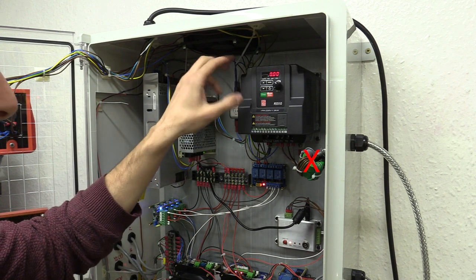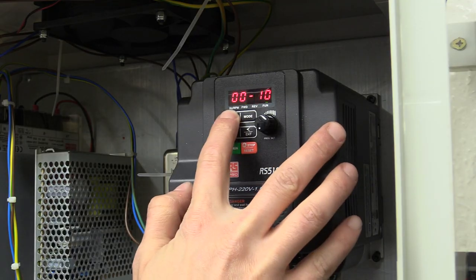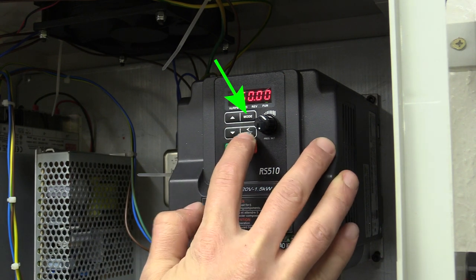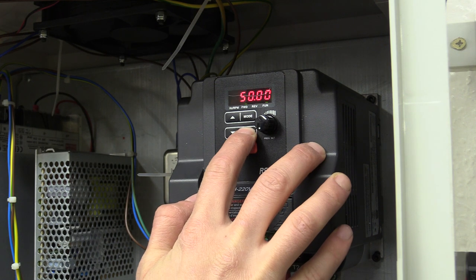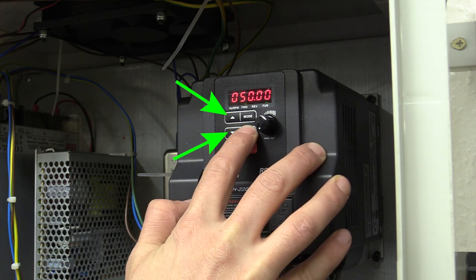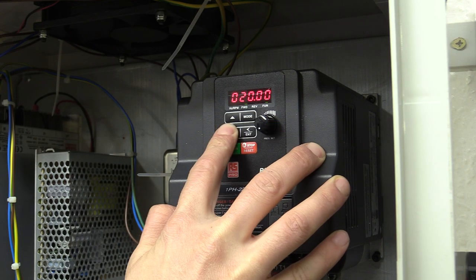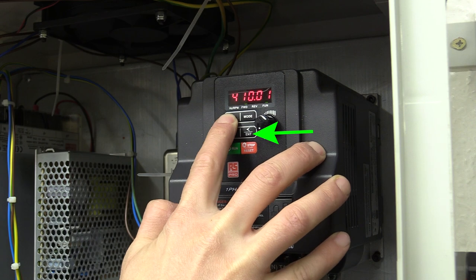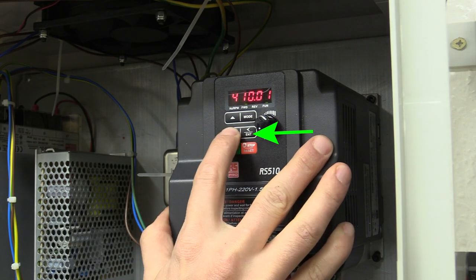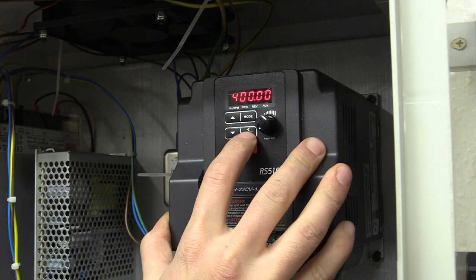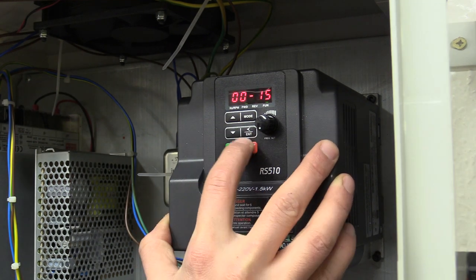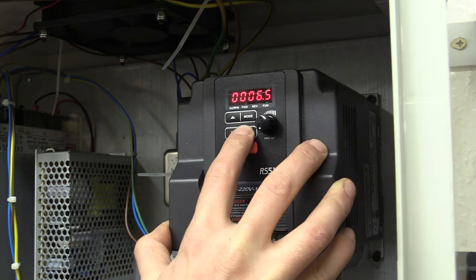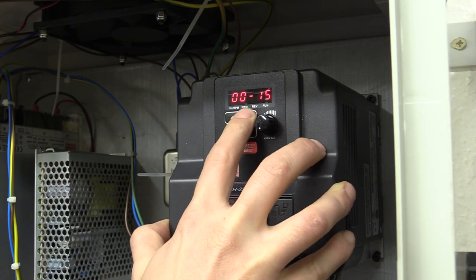To edit the different functions in the various groups on the VFD you first need to press the mode button several times until you see the function numbers. You can then change the digits with the up and down buttons and use the left arrow button that moves between the individual numbers. A long hold on the left arrow button, which also functions as an enter button, reveals the mode values, which you can also change with the up and down arrows. Once those are adjusted, a long hold of the enter button ends the edit and the new values are set.